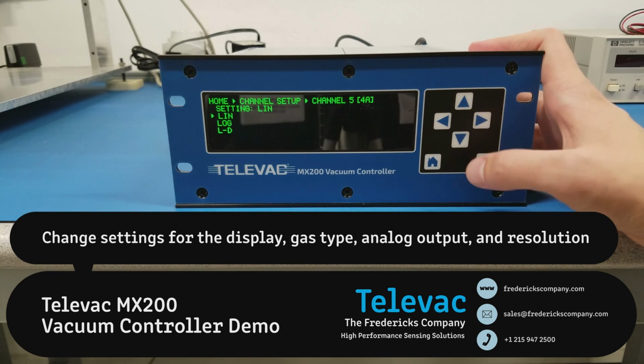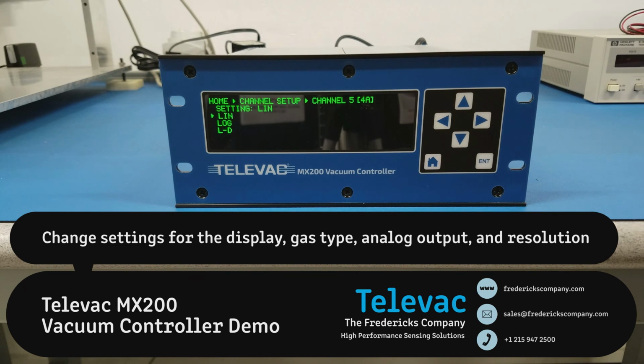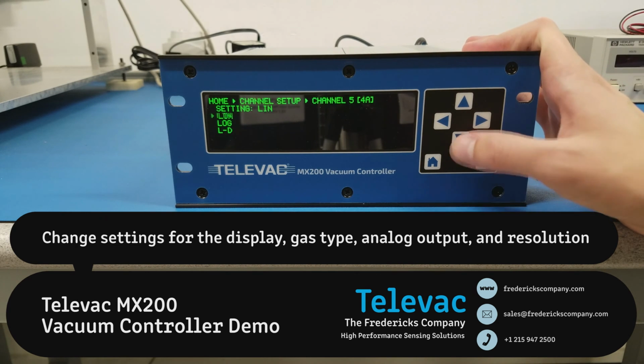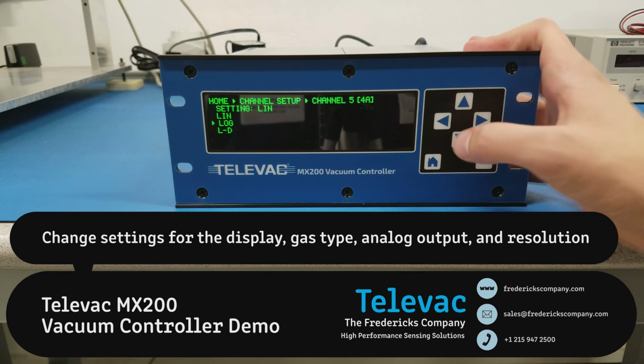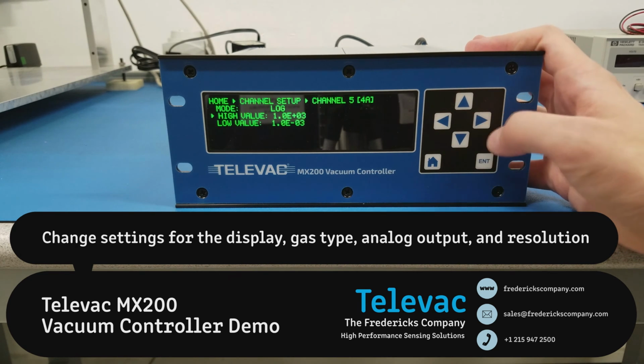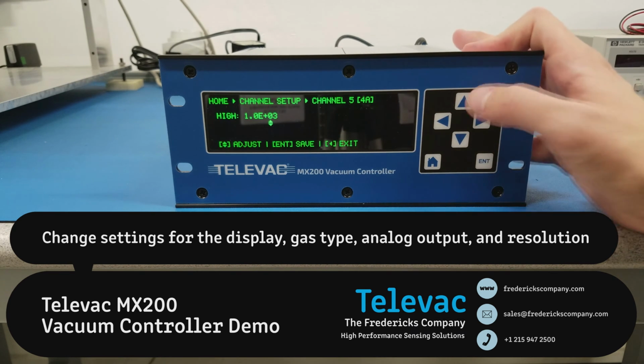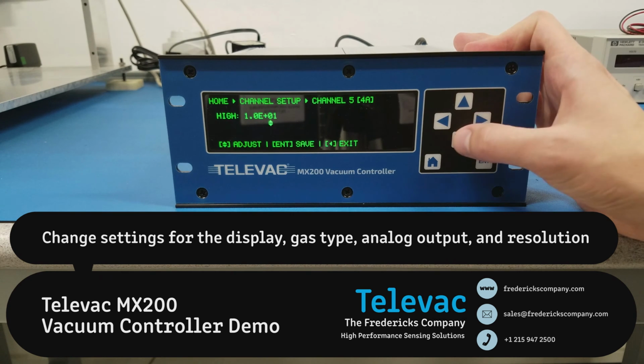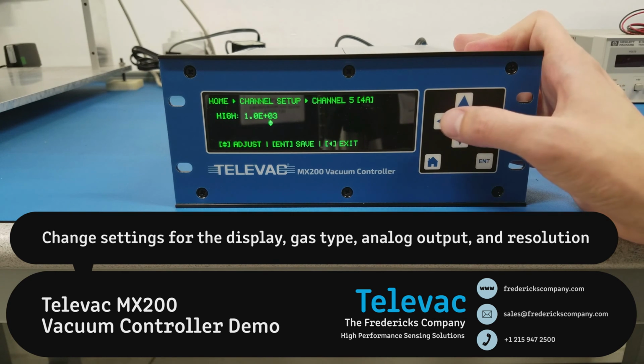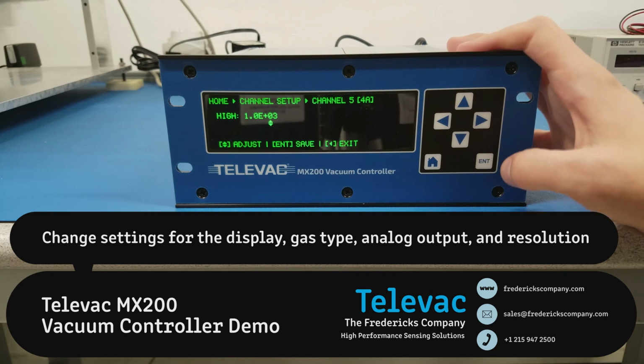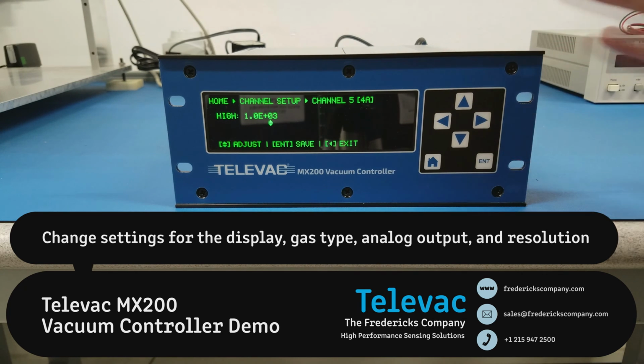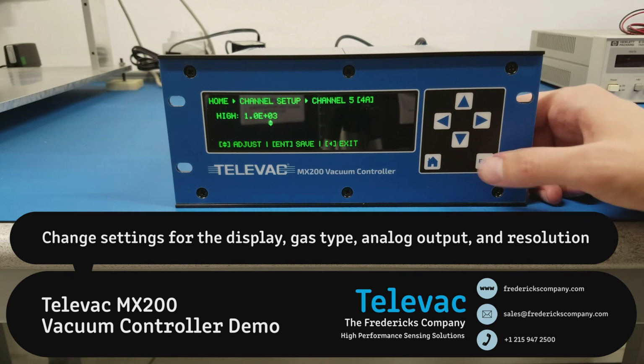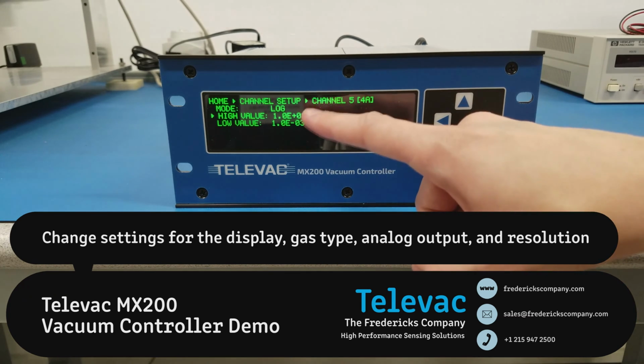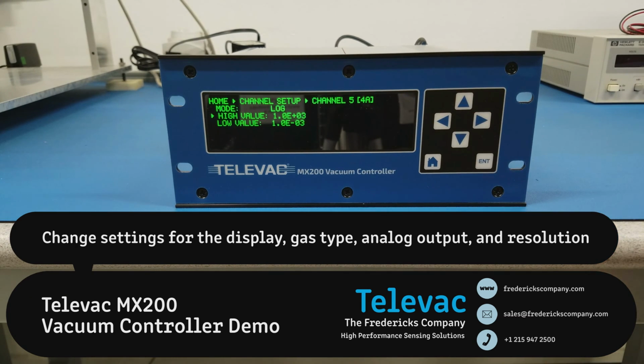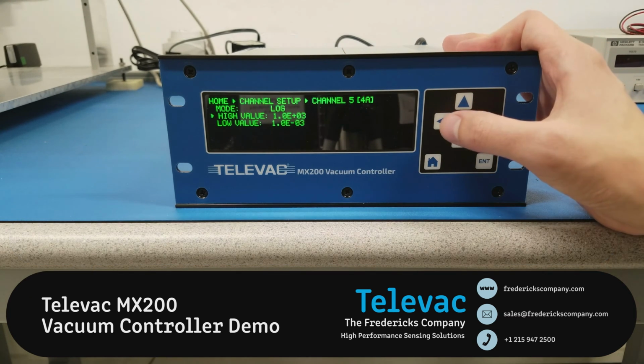So here you can select, these are going to be variable depending on the sensor type, but for the 4A, let's select log. Go back out. Then we can set the high and low value exponents. So I can adjust this up and down as long as this number is within 3 decades of the low value. So let's press enter to save that, and you can see here that that's saved in the memory of the unit.